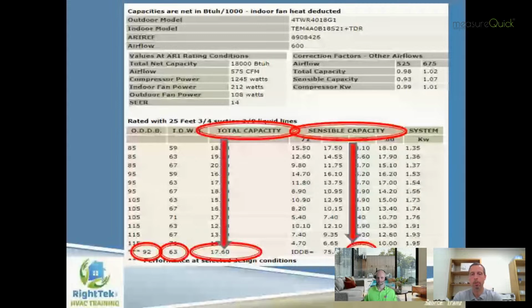We want to figure out what is the performance of that heat pump for both heating and cooling at exactly the same conditions that I ran my Manual J load calculation at. So for example, this particular house I did was in a climate where the summer design temperature was 92 and the winter design temperature was 23 degrees Fahrenheit. Well, I want to see the performance of this unit at 92 degrees in the summer, and I want to see it at 23 degrees outside temperature in the winter. And in addition to that, I also want to see the performance at the same indoor design conditions, which of course everybody knows Manual J currently is recommending: 75 and 50% relative humidity, or of course a 63-degree wet bulb.